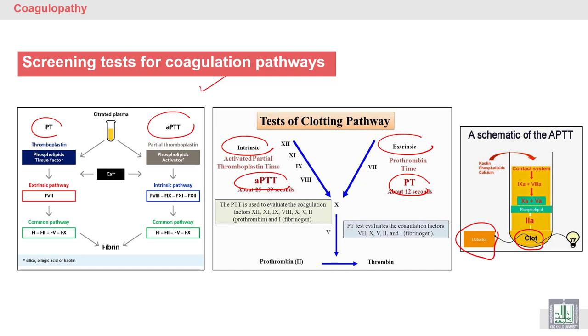Clot detection is now automated by instrument. Before, it was manual — detecting the first moment of clot formation visually. The PT is normally around 12 seconds and the PTT is 25 to 39 seconds. Now the instrument can detect the clot very easily using a detector.